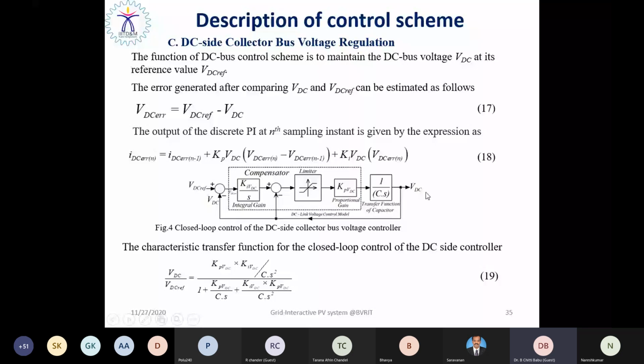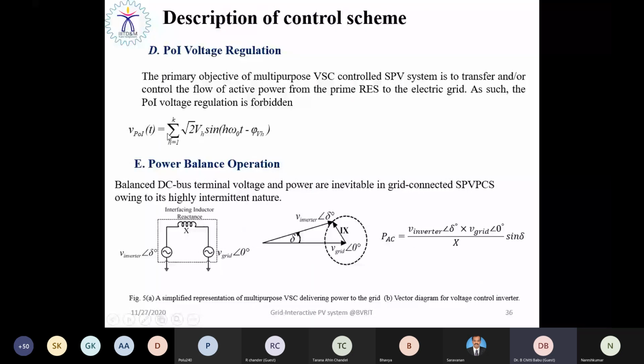So the DC link voltage regulation is very essential to maintain the power flow, so that the frequency can be regulated. And this is the corresponding transfer function, taking the ratio between the actual DC link voltage and the reference DC link voltage. So this control loop has been designed, and accordingly the gain has been calculated. So to tune accordingly, the DC link voltage has been controlled. And for the AC voltage regulation, as you are inverting 690 volt DC into 415 volt line to line, the 3 phase AC voltage should have only the fundamental component, where H is assumed to be 1, and it should be an RMS value of 450, right?